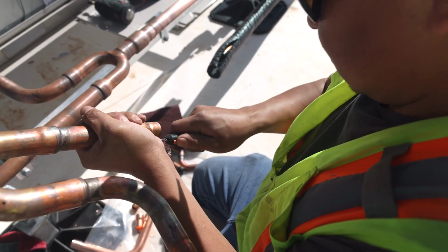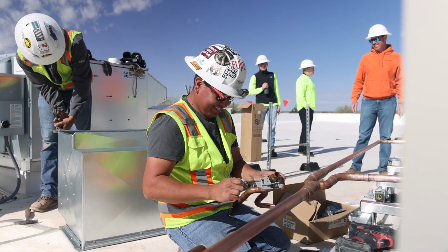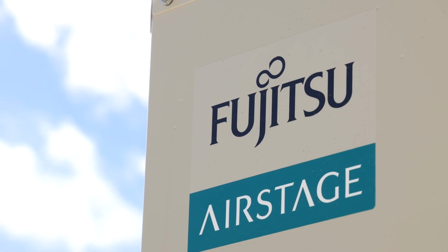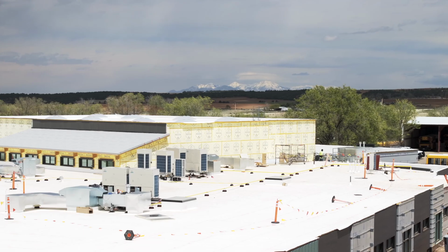When you combine all of that, you typically have a design that's oversized equipment compared to sea level, but it works very efficiently. And of all the projects I've done since I started VRF in cold climates, we've never had one problem due to the equipment capacity when designed correctly. With the equipment now going down to -15 without concerns, the defrost works fine, the altitude is not an issue. And with all of that combined, it makes for a very good design with the equipment.